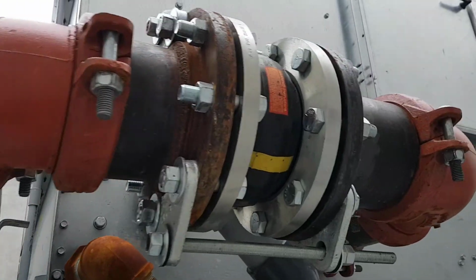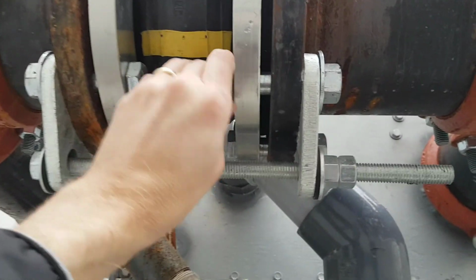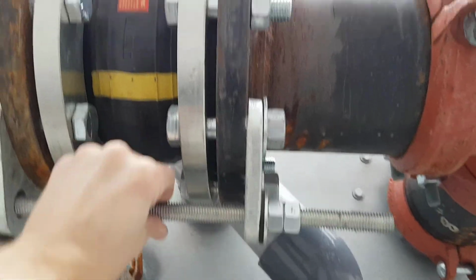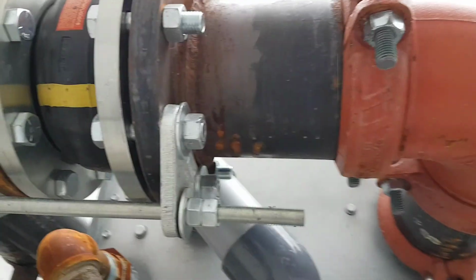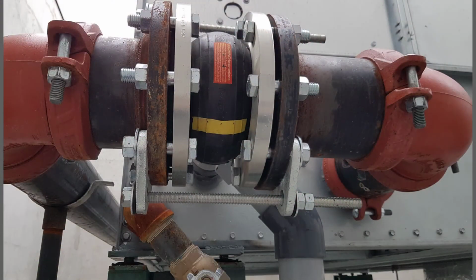The expansion joint at this connection uses EPDM material since it is outside and amazingly has the bolt heads in the right places. The control rods are loose. Out of all the joints we have seen, this one is just about perfect. If you were to go through the various questions, you would find that everything is okay. The expansion joint at the top of the tower is pretty good. My concerns on this one were the bolts being backwards again, the control rods not being loose, and there being a possibility of the joint helping to hold up some of the pipe on one side or the other. But nothing dangerous and nothing that I would say needs to be fixed or adjusted unless there were a noise problem. So I was willing to call it close enough and maybe okay.